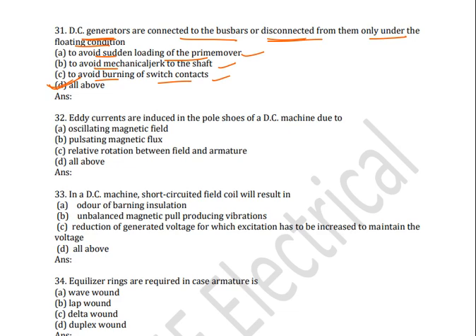Regarding floating condition — floating condition means the induced voltage in the generator equals the bus bar voltage, so no load will be delivered and it will be disconnected from the bus bar. If the induced EMF is more than the bus bar voltage, then only it will be connected and load will be delivered.